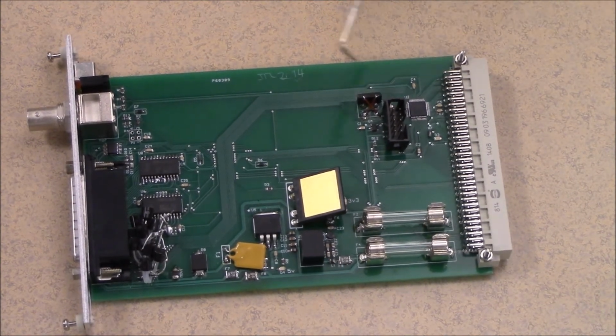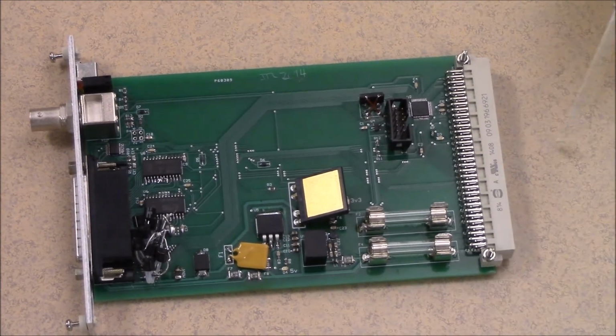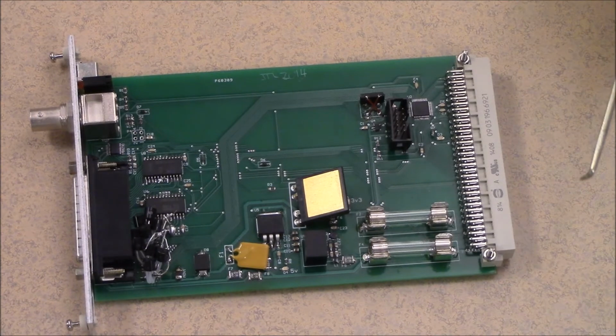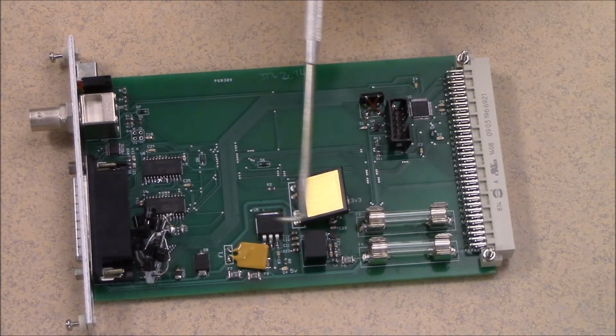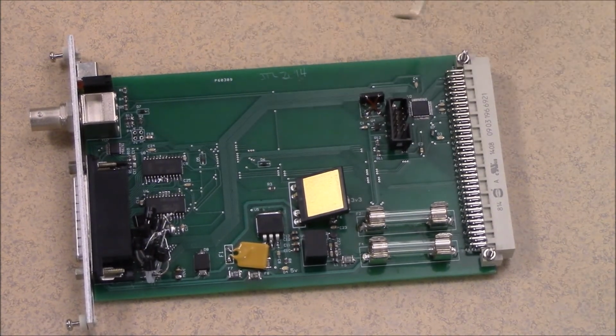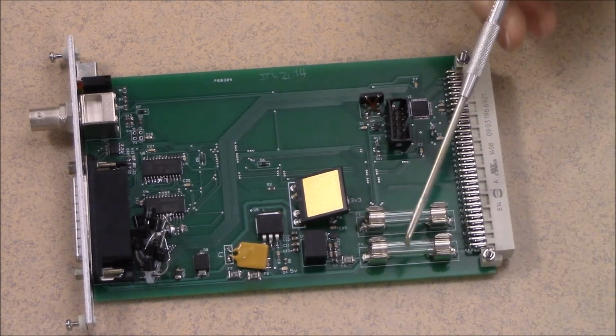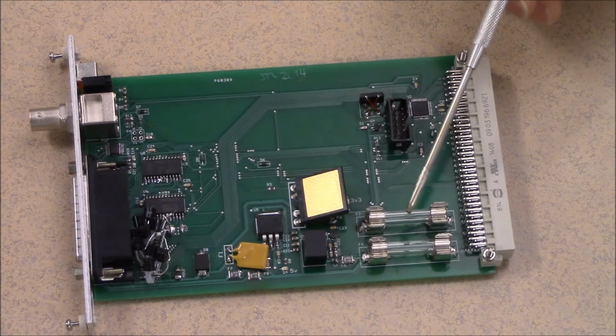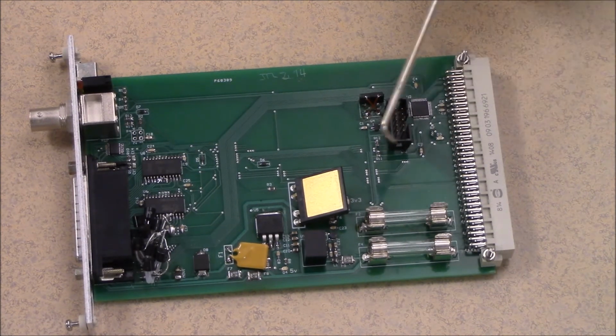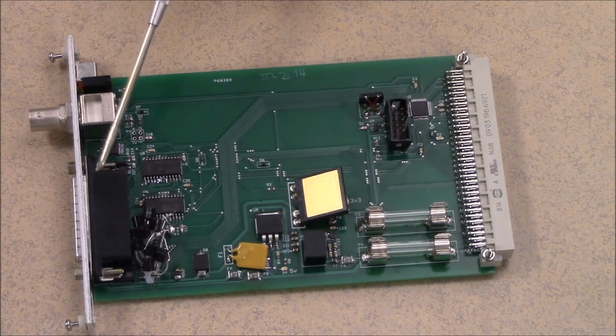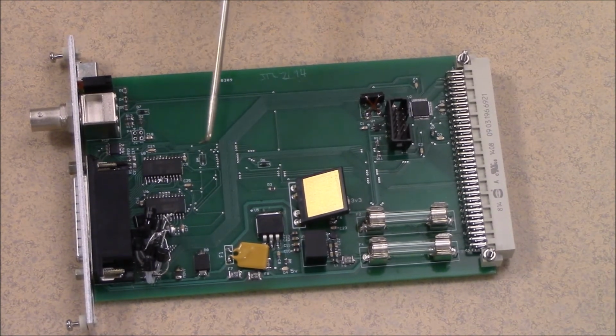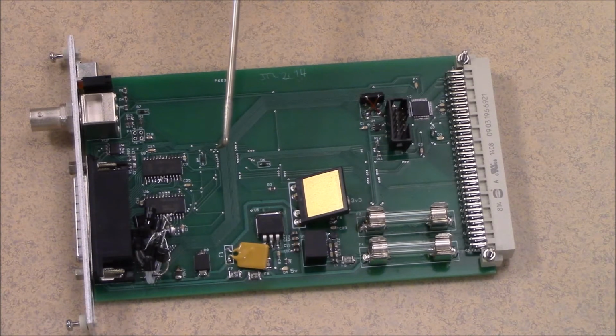Here we have the relay control module, critical for enabling our calibration of the device. It has a variety of fairly unique features compared to the others and is both simpler and much more complex in certain ways. Here we have the same DIN backplane connector, but there are 2 glass fuses, and these fuses lift both ground and the 24-volt power rail and are used to protect the device in case of a fault within any of the controlled relay loads, based on a variety of experiences we had last semester.